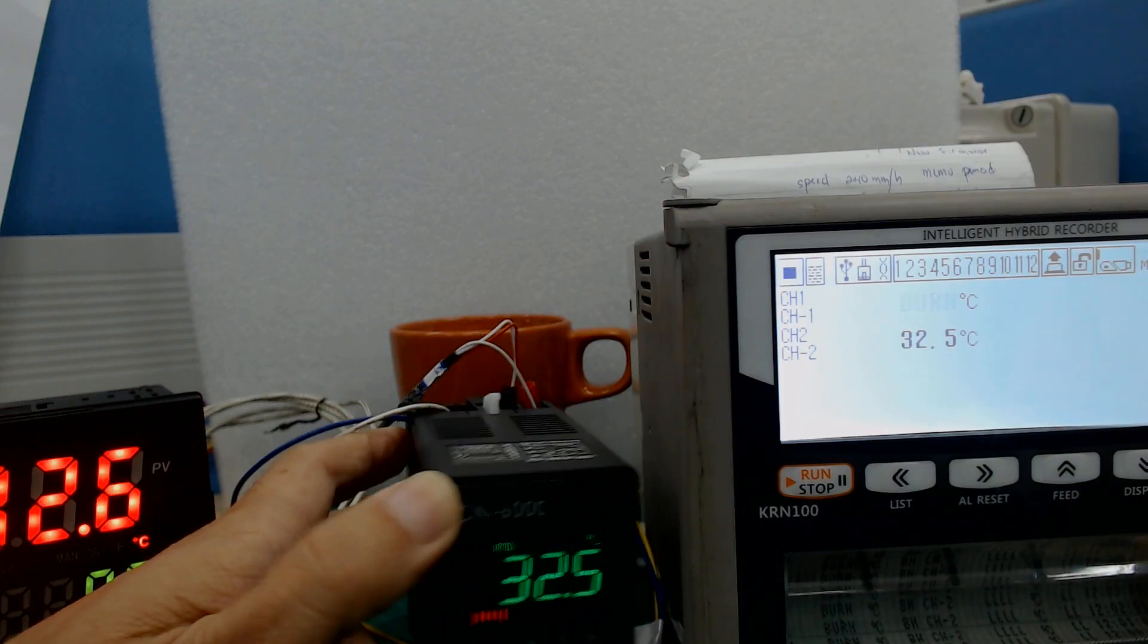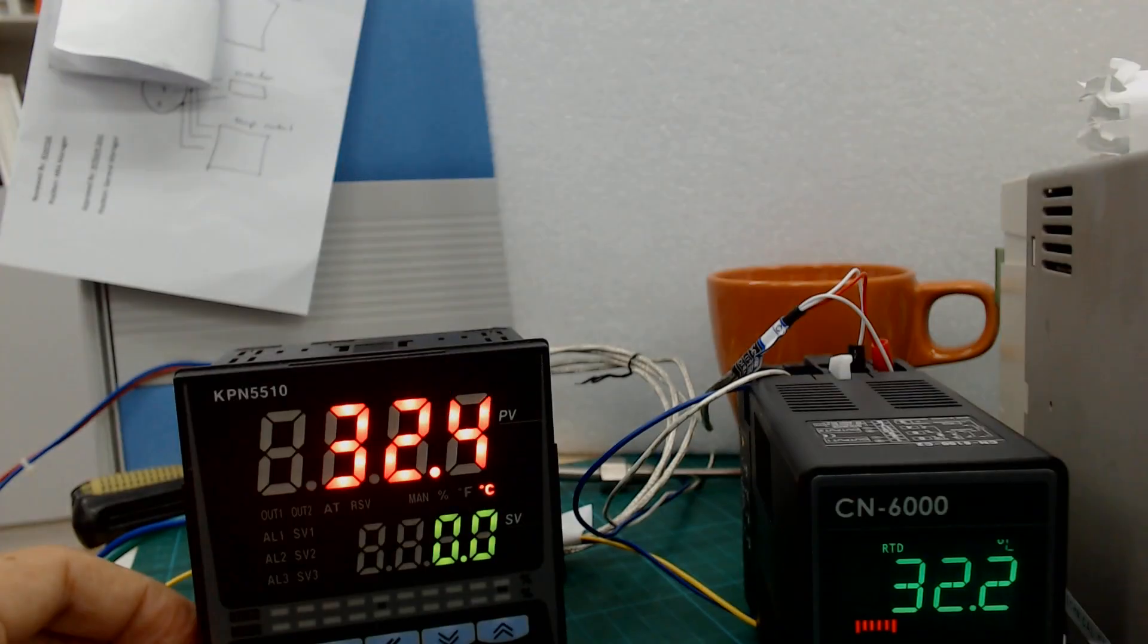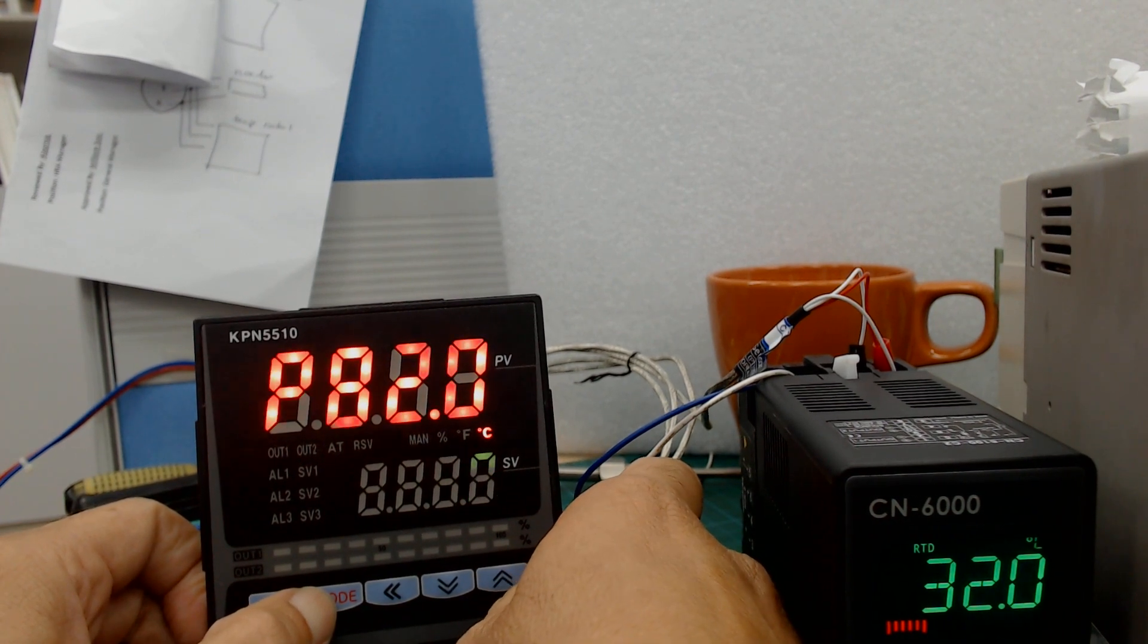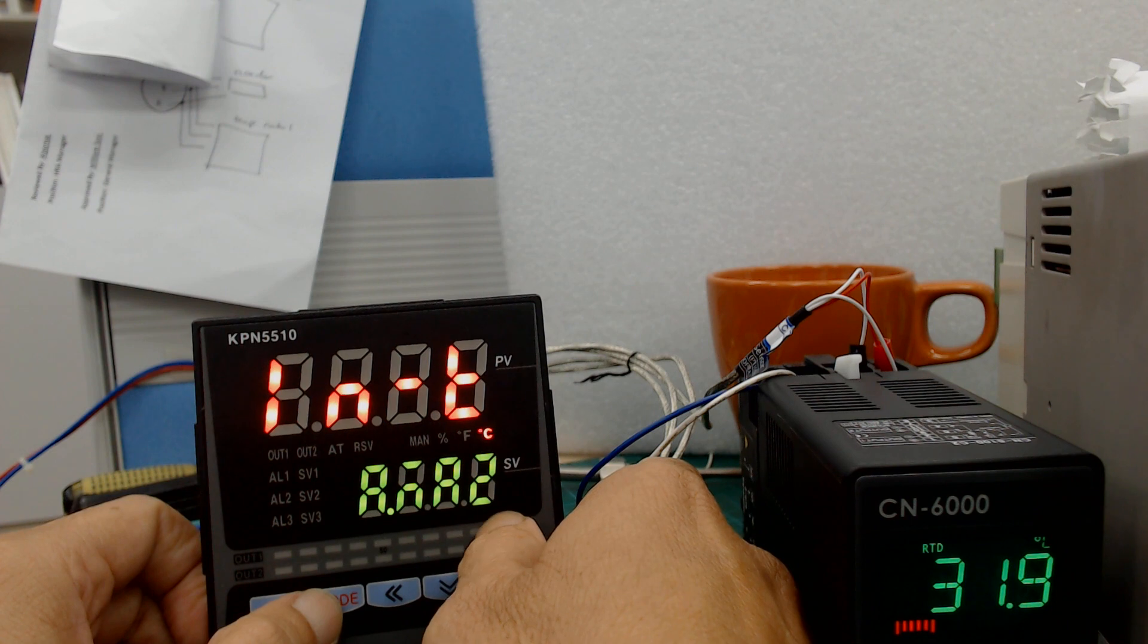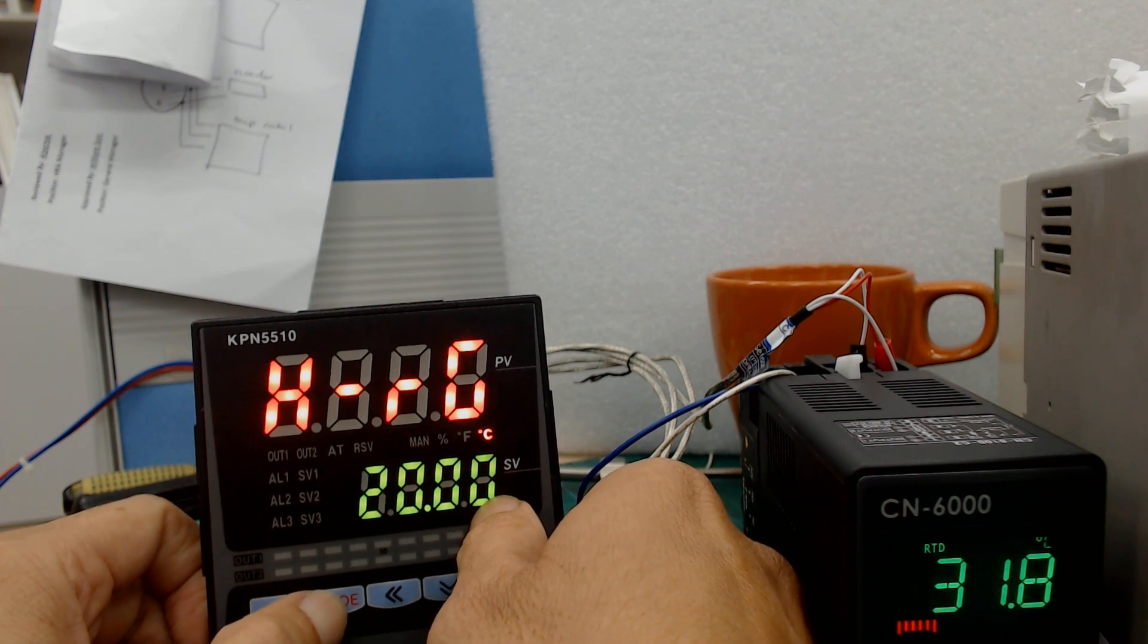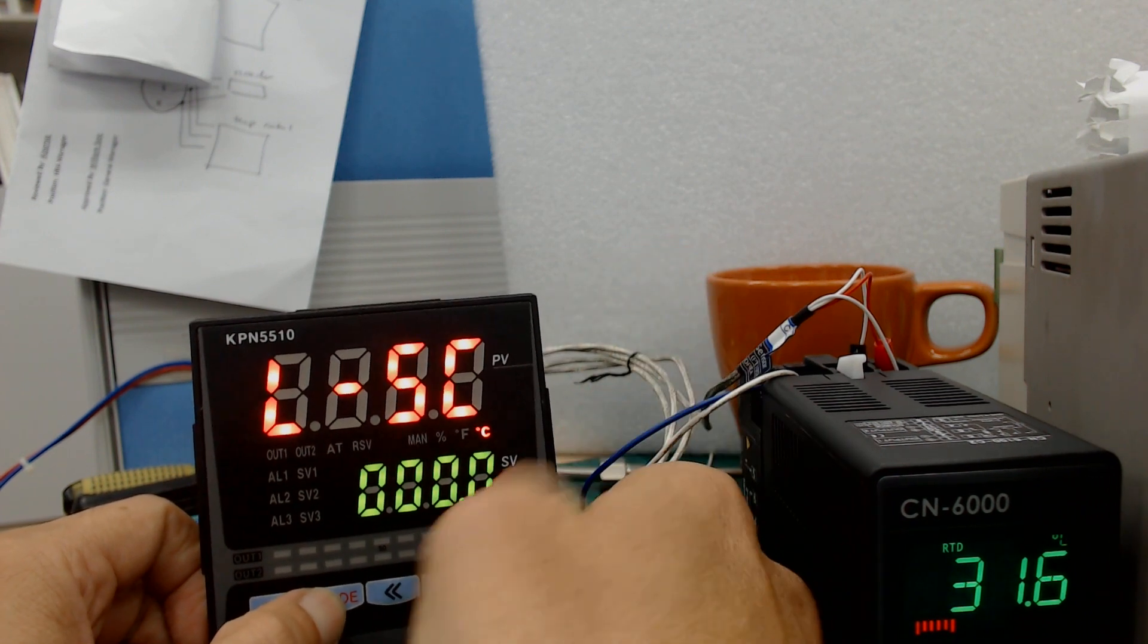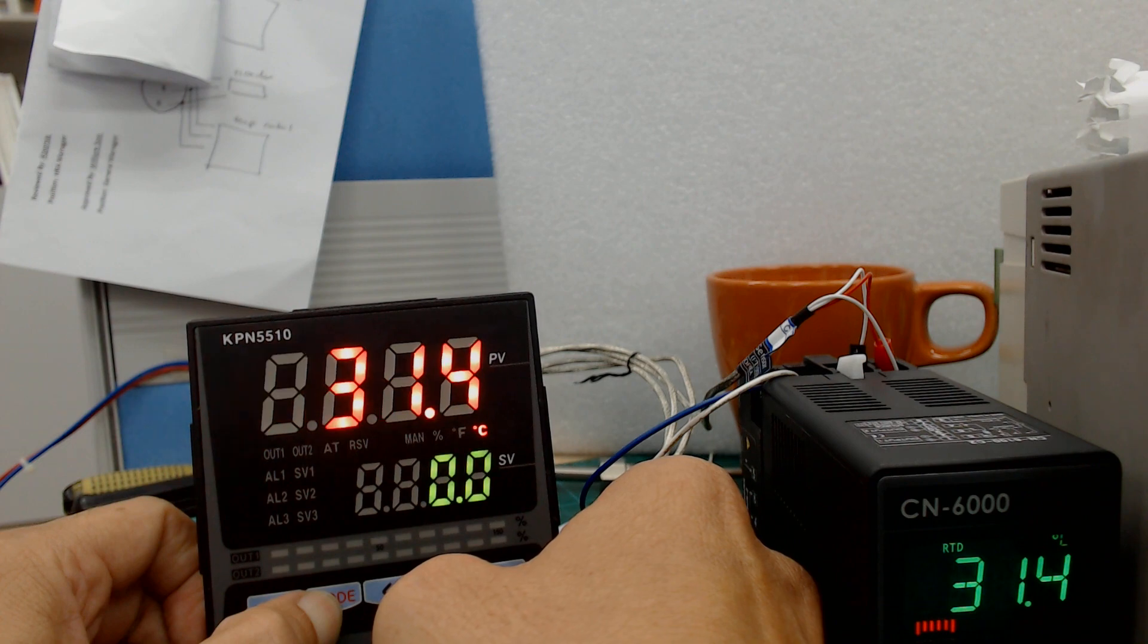Now for the KPN, input is 4-20mA. Press mode, parameter 3. You go to parameter 3, ANA2 is analog 4-20mA input. Low range of 4mA, 20mA high range. The scaling is zero, same as the converter. High scale 120 Celsius. That's all for the KPN.